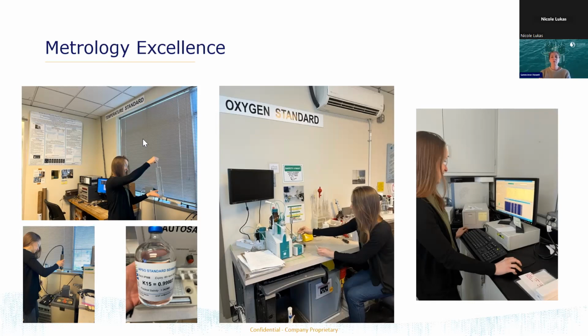And so we use a secondary transfer standard. So after we have calibrated our platinum resistance thermometer in those fixed point cells, then we actually go ahead and calibrate a set of SBE3 temperature sensors that we have sub-selected because they demonstrate very low drift. So these are very solid sensors in terms of not moving. They're very, very stable over time. So we calibrate those to our platinum resistance thermometer, and now we have traceability all the way back to our NIST standards of those fixed point cells.